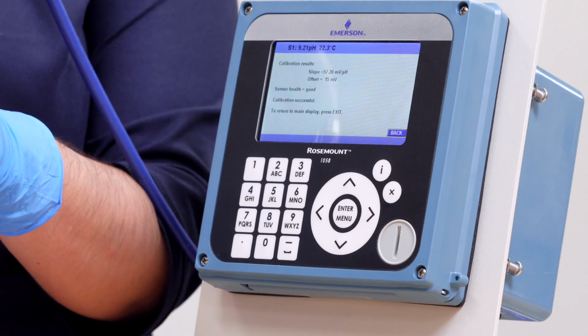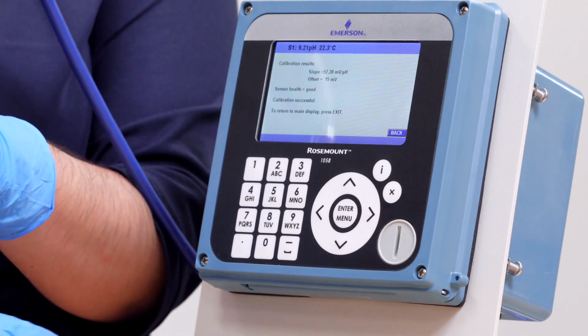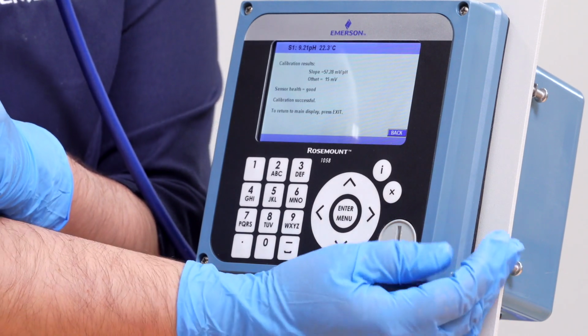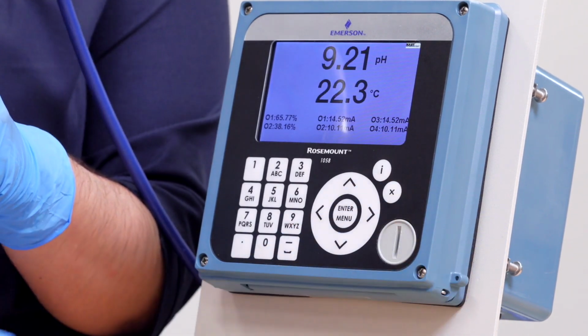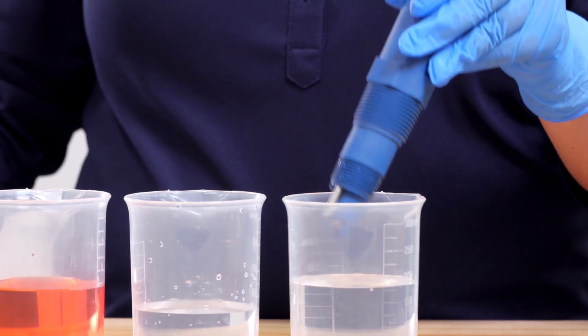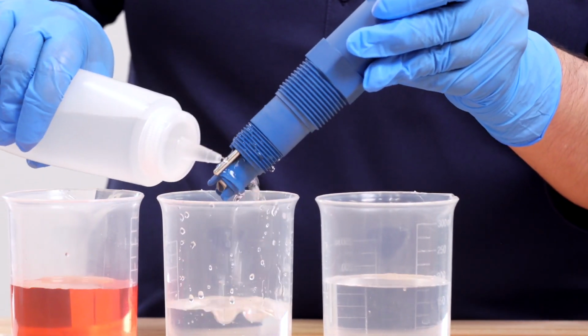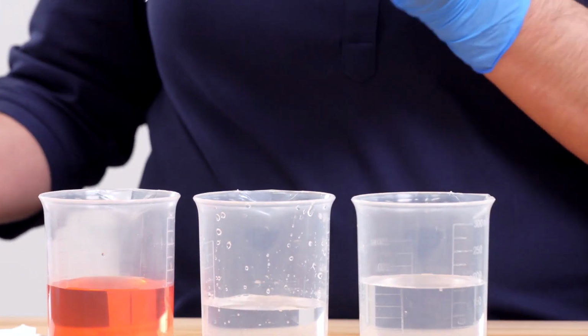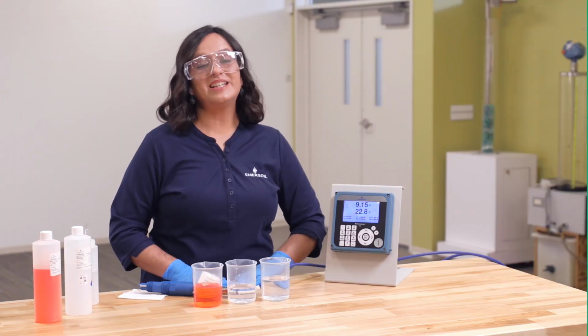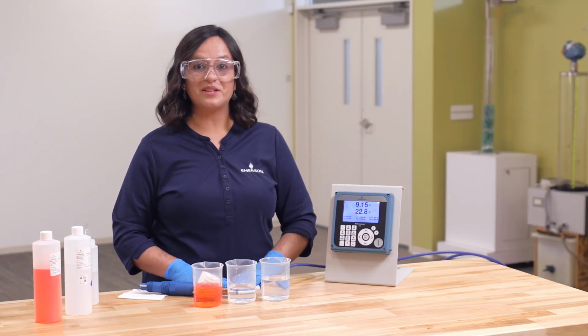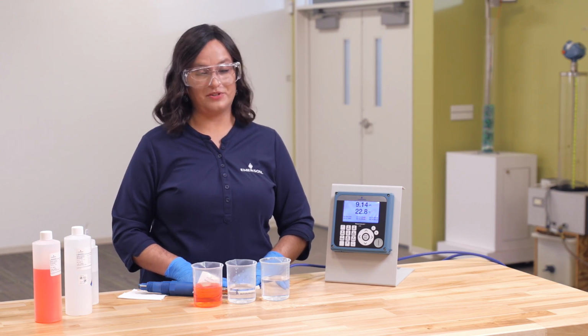The transmitter will return to normal functioning after you select X or Exit. Now, rinse the sensor a final time and place it back into the process. This completes the overview of how to auto-calibrate a pH sensor with two buffer solutions.